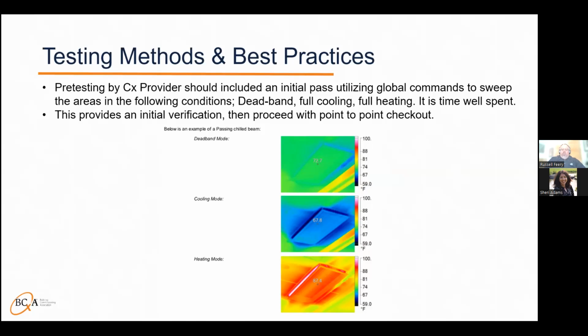So we'd go through and force everything into a dead band, go through and shoot the ceiling. Anything that wasn't functioning, the controls contractor and general contractor took notes and they went back and addressed them prior to us doing our full point-to-point verification. And then in cooling mode, you can see where everything is forced into full cooling globally, and you can walk through and actually see the chill beam radiating kind of a blue color and a temperature that indicates that it is in cooling mode. And then same in the heating mode.